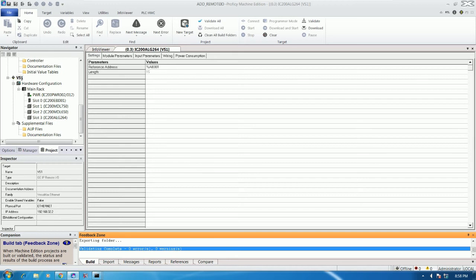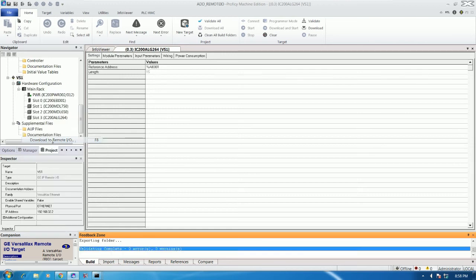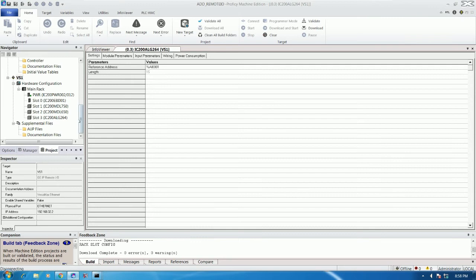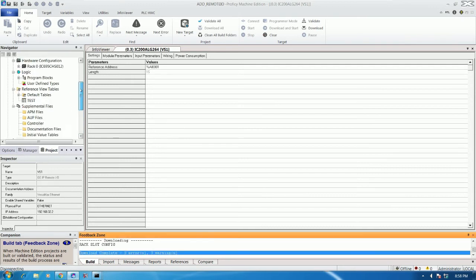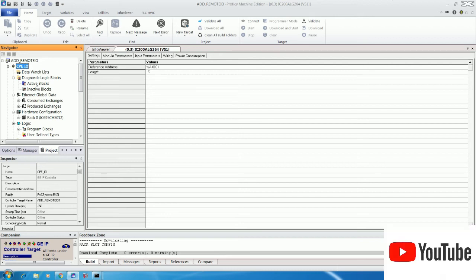Right-click and validate to check for errors — no error occurred. Then right-click and download to the remote I/O, then click OK. Download completed successfully with no errors. Now set it as the active target, then take out the LAN cable from the remote I/O and reconnect it to the CPE.